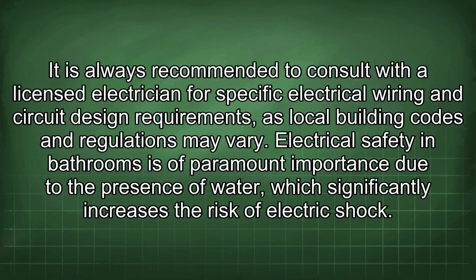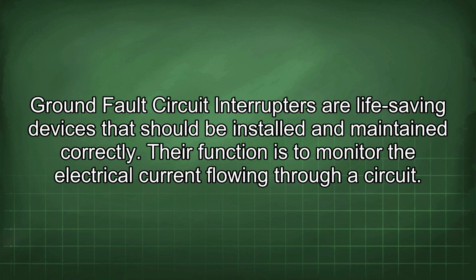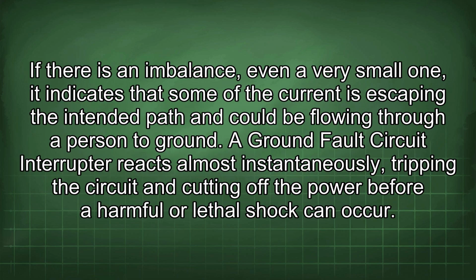Electrical safety in bathrooms is of paramount importance due to the presence of water, which significantly increases the risk of electric shock. Ground fault circuit interrupters are life-saving devices that should be installed and maintained correctly. Their function is to monitor the electrical current flowing through a circuit. If there is an imbalance, even a very small one, it indicates that some of the current is escaping the intended path and could be flowing through a person to ground.